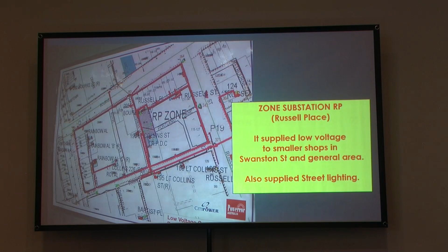It was also a zone substation or area substation supplying 400 volt power in the general area. Let's have a quick look at what that involved. That's a 6.6 thousand volt paper insulated lead sheath cable coming into the terminal box of the transformer, which I think is a 2 MVA transformer, the output of which is fed through those isolating links and an air circuit breaker onto the bus bar, which in turn feeds red, white and blue phases of the 3-phase circuits heading out of the building. On the right here is a public lighting panel, as it was called.